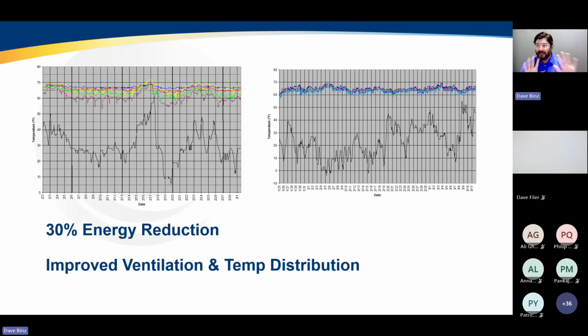So what you're seeing here is a before and after of temperature loggers throughout the facility. On the left, this was your before with many unit heaters. The black bar is the ambient temperature outdoors, and the multicolored lines are various temperature sensors throughout the facility, floor to ceiling, wall to wall. And so you may see in some cases, where we get to roughly 5 degrees ambient here, we were seeing 55 degrees in one area and almost 68 degrees in another area.